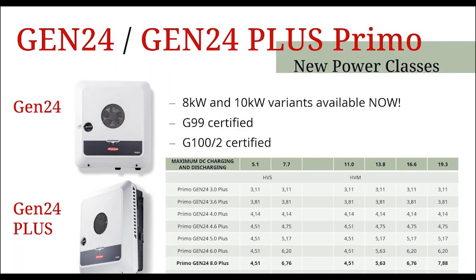The next feature to have a look at is the new power classes that are available on our Primo single phase unit. So we now have an 8 kilowatt and 10 kilowatt Gen24 and Gen24 Plus. So again, these are G99 and G100 certified, and they enable you not only to generate a higher power, connect more panels to your inverter, but they also enable slightly higher charge and discharge rates into a battery. So if you have an HVS 7.7 battery or an HVM 19.3, you'll see that you're getting a higher output power with these new higher power classes.